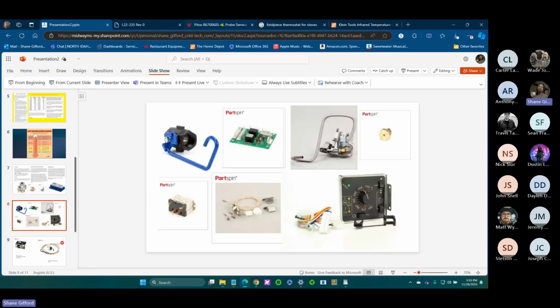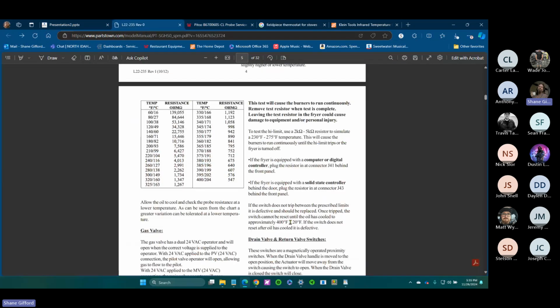Yep. And that's because of a difference in how it's wired. Like a lot of the systems that we work on, refrigeration, air conditioning, whatever, you can have a lot of your loads wired in parallel, meaning if one of them drops out, right? If your condenser fan motor drops out, you're not going to lose your compressor because they're wired in parallel. Heating appliances wire everything in series, or they wire it from the board. And what the board will do is send out a signal, and if that signal comes back, the board recognizes that power has gone through that safety, and therefore, okay, next step, let's send power up to the next step.